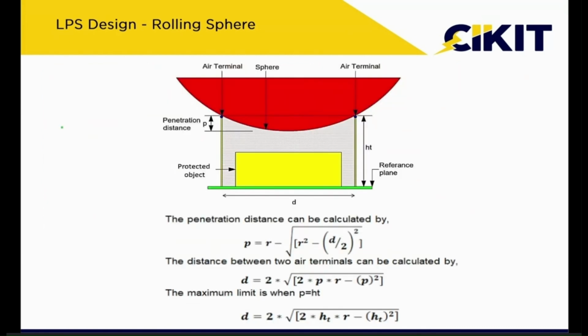In all the cases, we cannot roll the sphere over the structure and check whether the sphere is making contact or not. So that is the reason the standard has provided the formula for calculating the distance between the two air terminals so that the sphere won't make any contact with the structure to be protected. So we can use this particular formula for calculating the maximum distance between the two air terminals. The point which we have to note down is that in this particular methodology, we are calculating the maximum distance between the two air terminals, whereas in the protection angle method, we are calculating the radius of protection. So these two are not the same, these two are different.